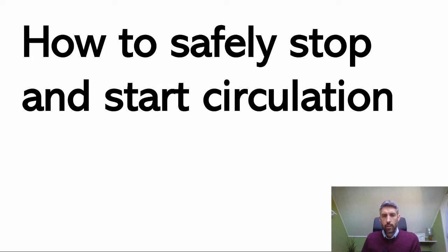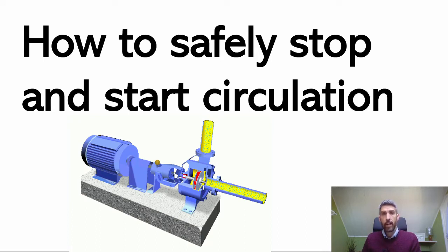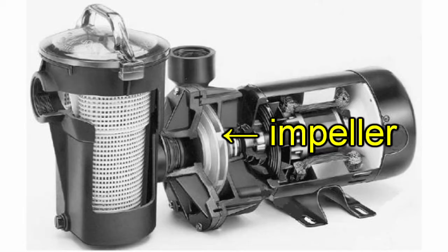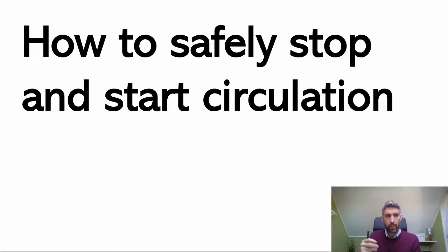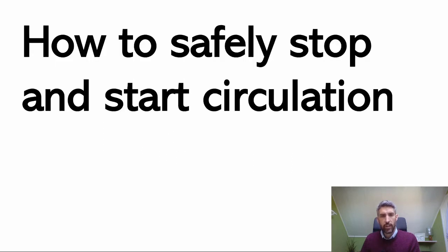What this describes is where the circulation pumps and the pipework in that vicinity loses the water, because all of that pipework should be flooded with water. The circulation pump impellers need to be drawing on water rather than air. What causes a loss of prime is where the plant room is orientated above the level of the swimming pool itself.